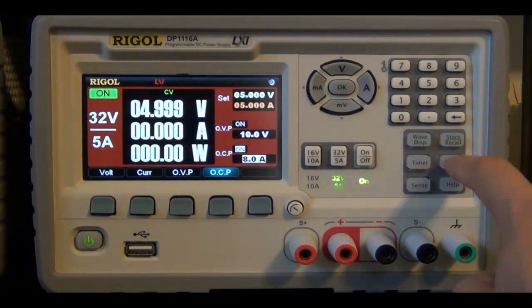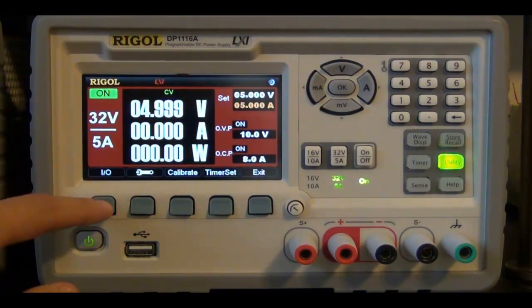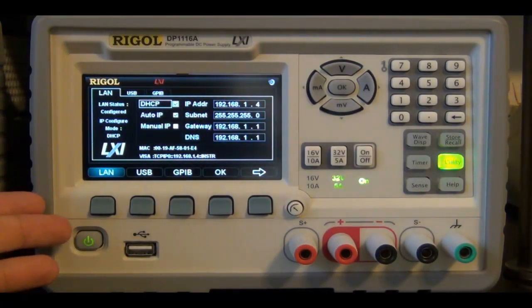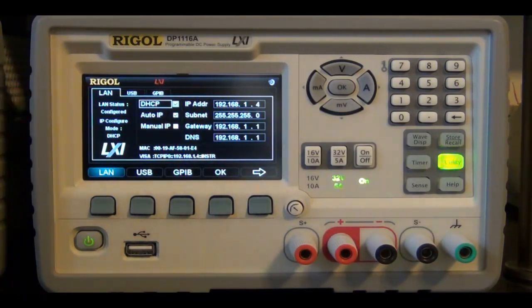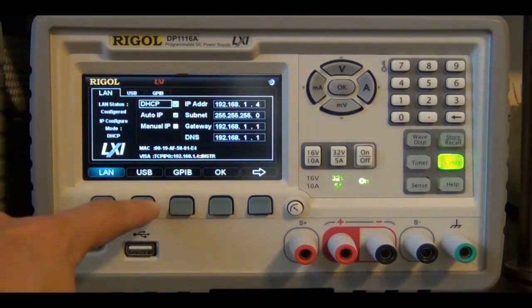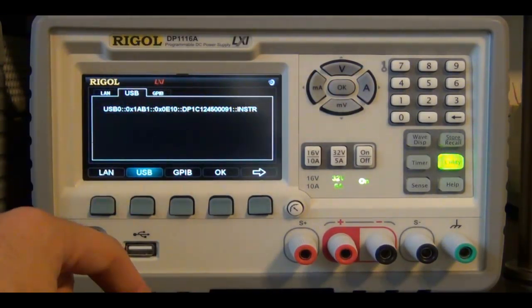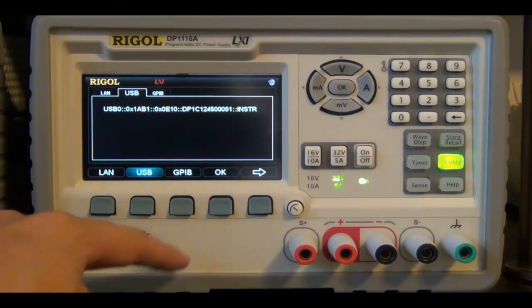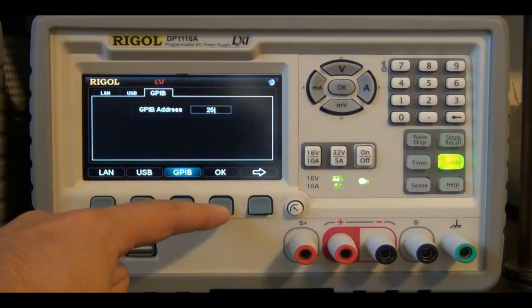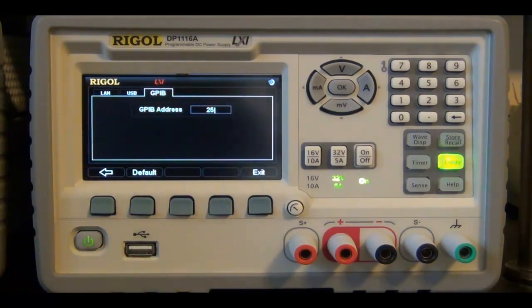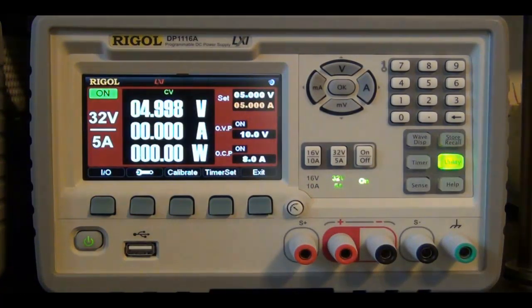It has the utility button, of course, which gives you soft menus. You can click the I/O button and you have LAN, USB, and GPIB. I have already configured the LAN, you can see right there. You can configure the USB, there's a USB address for it, so you can talk to it using the drivers. There's, of course, the GPIB address 25, and there's a whole bunch of other settings.